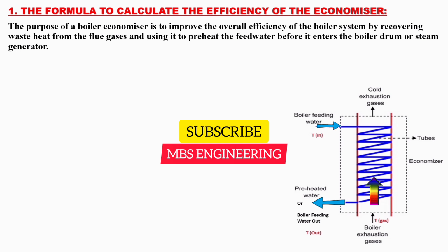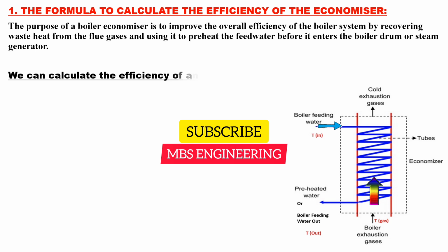This preheating process occurs through heat transfer between the combustion gases exiting the boiler and the feedwater, as illustrated in the accompanying picture. Typically, economizers are constructed with finned tubes made from carbon steel, stainless steel, or cast iron. The water to be heated flows through the tubes, while the combustion gases produced during the process circulate around the outside of these tubes. Next, we will learn and calculate the efficiency of an economizer using the following method.